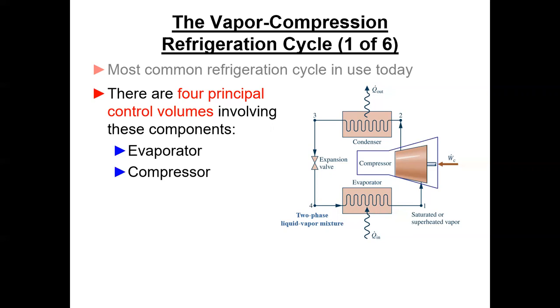We have at least saturated or superheated vapor coming out of the evaporator because it's going into the compressor, and the compressor doesn't like any liquid droplets. We put work in to compress the refrigerant vapor from low pressure to high pressure. It comes out as a fairly high temperature, high pressure superheated refrigerant vapor out of the compressor.